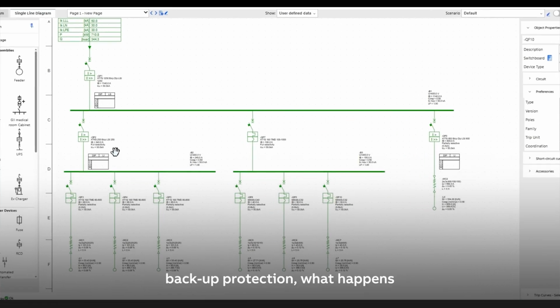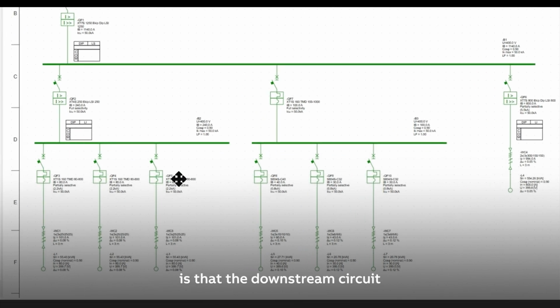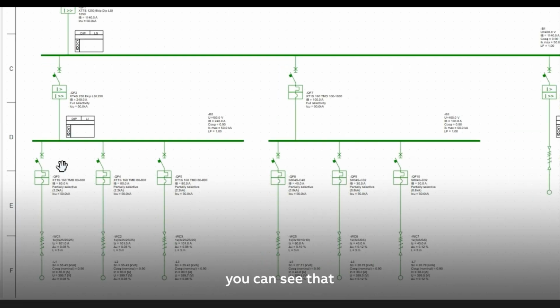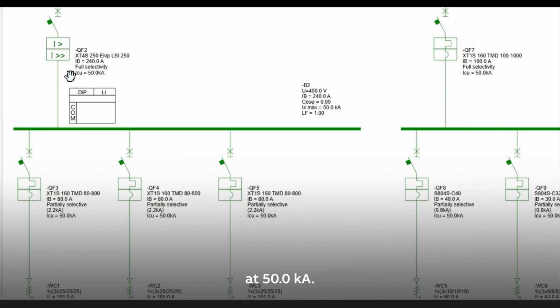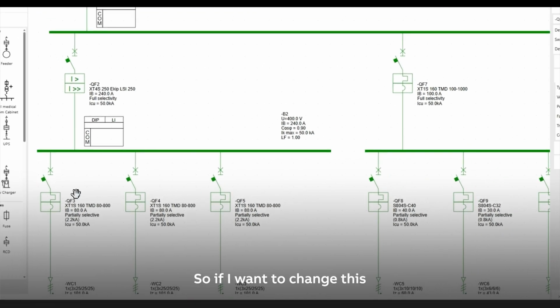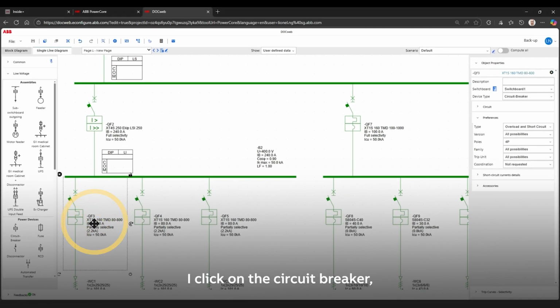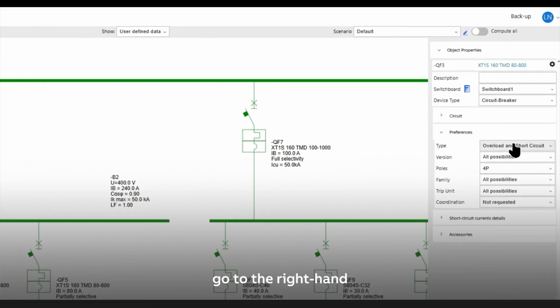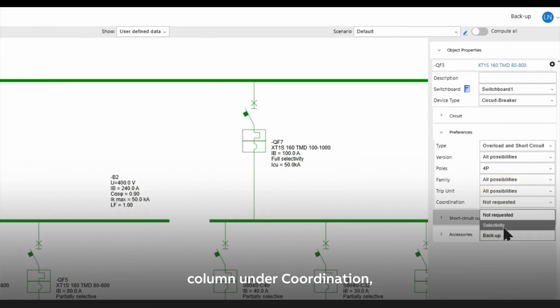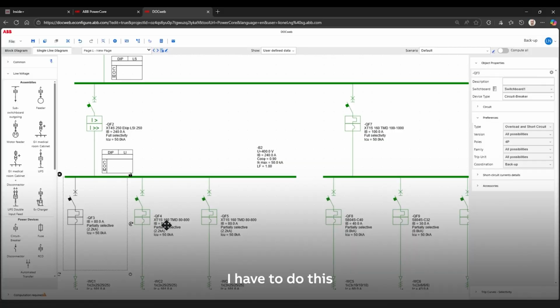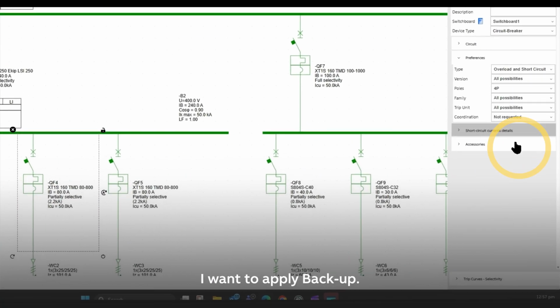But if I'm willing to use backup protection, what happens is that the downstream circuit breakers can be selected to a lower ICU rating. Currently, you can see that all the breakers are rated at 50 kiloamperes, so if I want to change this to backup protection, I click on the circuit breaker, go to the right-hand column under Coordination, and choose Backup. I have to do this for all the breakers where I want to apply backup.